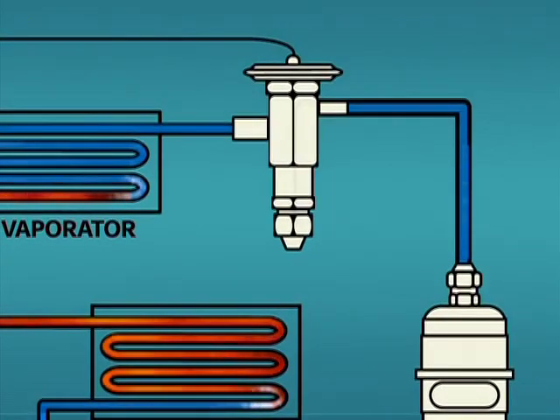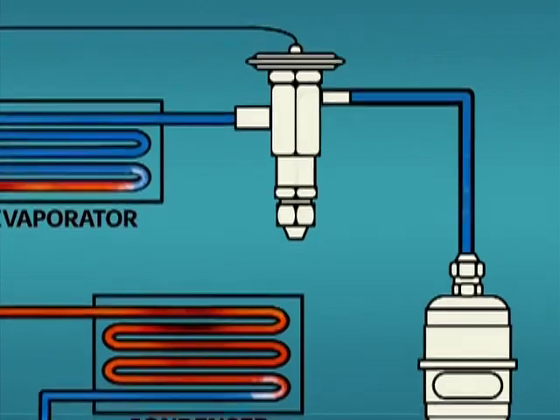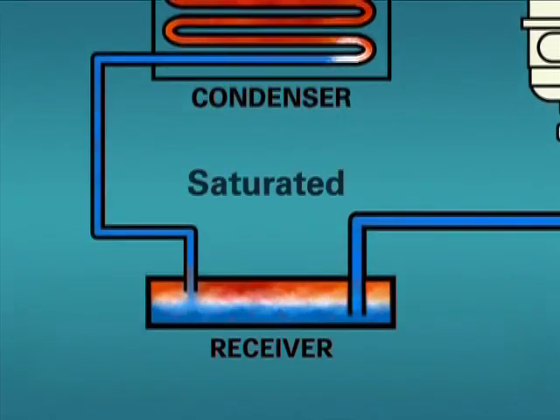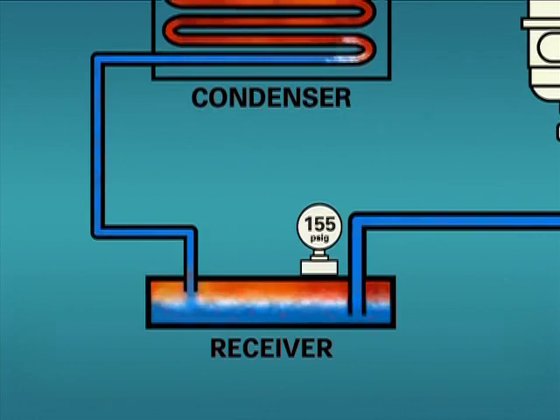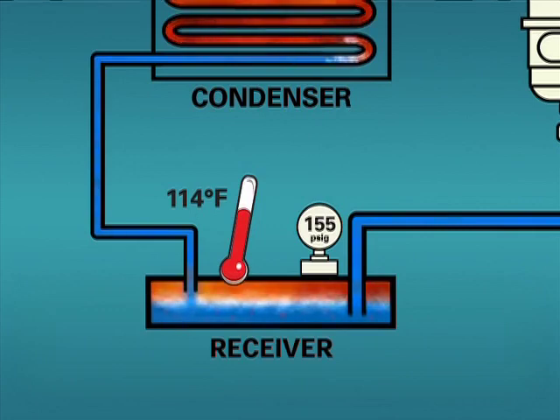With most systems, one can expect to find the refrigerant in the liquid line to have some amount of subcooling. In particular, systems employing a TEV should have subcooled refrigerant liquid entering the valve. When a system employs a liquid receiver, we will find saturated refrigerant at the liquid vapor interface in the receiver. If the measured pressure in the receiver is 155 PSIG, we know the temperature at the refrigerant level to be 114 degrees Fahrenheit. The fact that saturated refrigerant exists in the receiver does not mean subcooled liquid cannot exist in a receiver. If the condenser provides subcooled liquid to the receiver, subcooled liquid will be present in the receiver also.